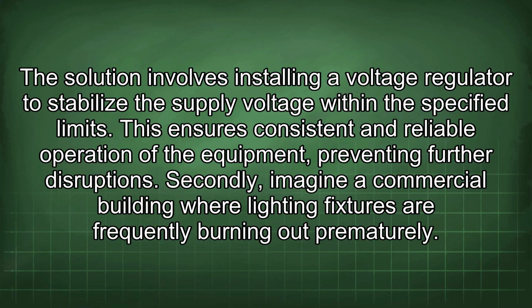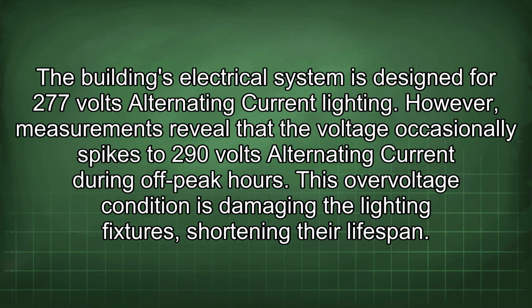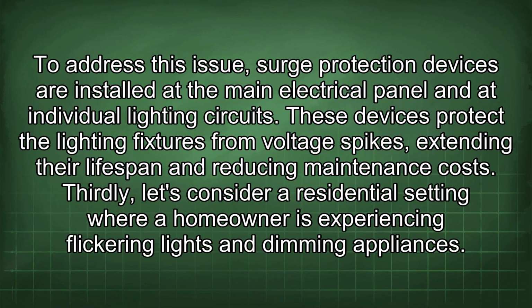Secondly, imagine a commercial building where lighting fixtures are frequently burning out prematurely. The building's electrical system is designed for 277 volts alternating current lighting. However, measurements revealed that the voltage occasionally spikes to 290 volts alternating current during off-peak hours. This overvoltage condition is damaging the lighting fixtures, shortening their lifespan. To address this issue, surge protection devices are installed at the main electrical panel and at individual lighting circuits. These devices protect the lighting fixtures from voltage spikes, extending their lifespan and reducing maintenance costs.